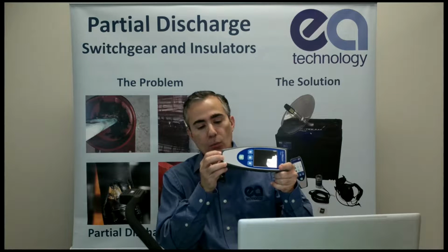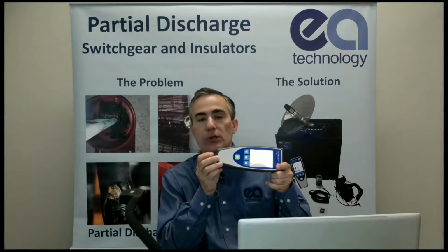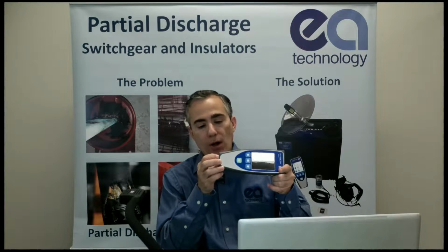The UltraTEV Plus 2 has multiple communication methods to accommodate personal preferences and IT department security rules. Included is an 8 GB microSD memory card, and the system supports up to 64 gig. The card is located at the bottom of the instrument in a spring-loaded slot, and a gentle 1 mm fingernail push extracts or installs the card.